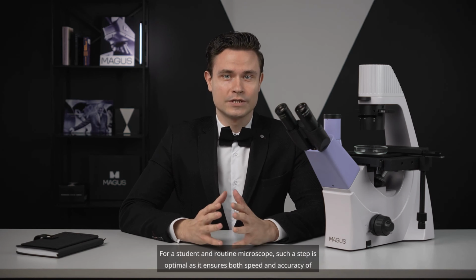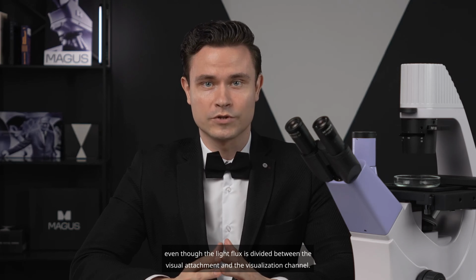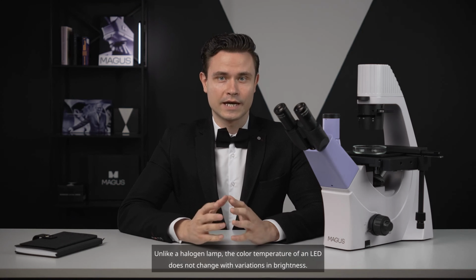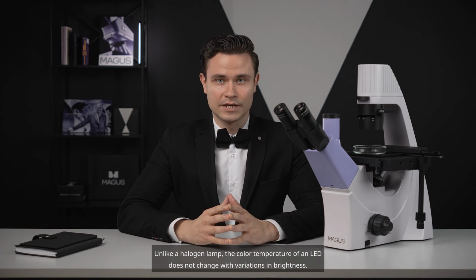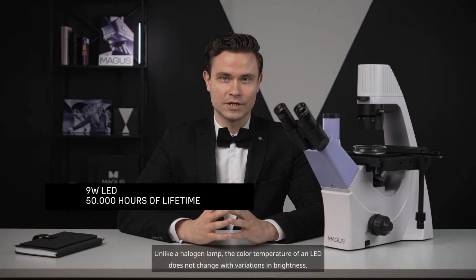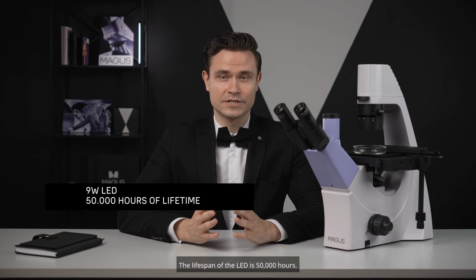Light source. The 9W LED brightly illuminates the object. The intensity of the light is sufficient for both bright field and phase contrast methods on all objectives, even though the light flux is divided between the visual attachment and the visualization channel. Unlike a halogen lamp, the color temperature of an LED does not change with variations in brightness. The lifespan of the LED is 50,000 hours.